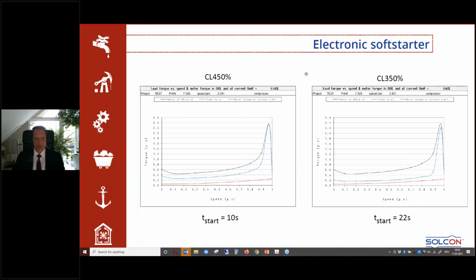Here you can see two examples of what is happening in a motor with respect to starting torque when you are applying different current limit values. In this case, it's 450%. There is still quite some margin between the reduced torque and the torque speed curve of the load. And here it is reduced. And this reflects back and has consequences in the starting time. In this case, for this particular example, it is 10 seconds versus 22 seconds.